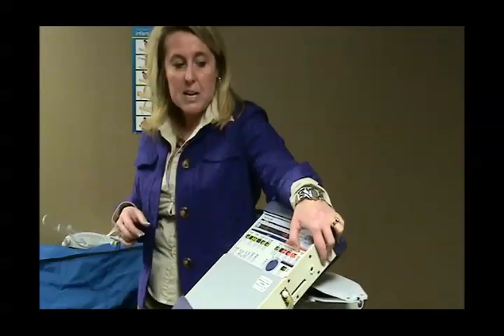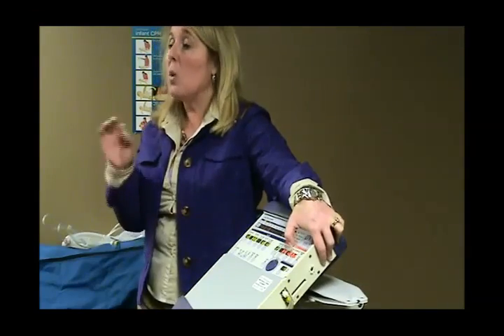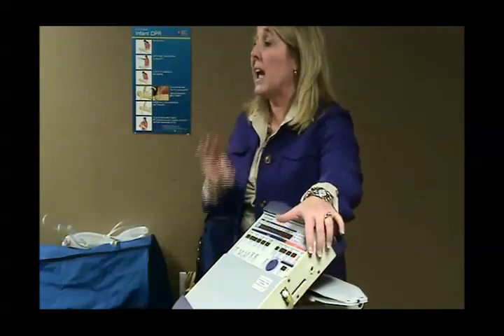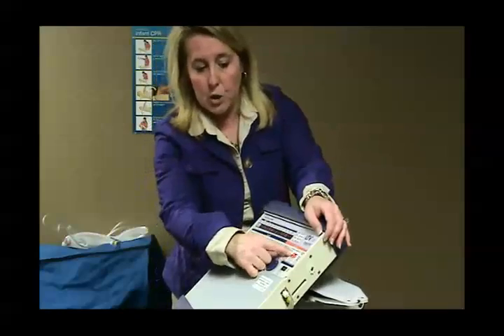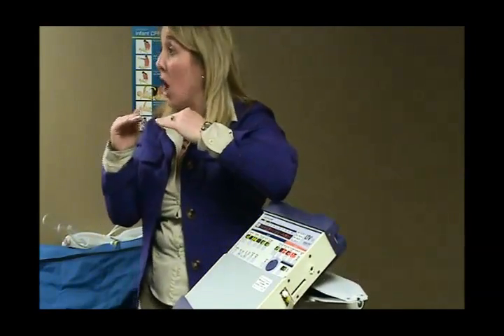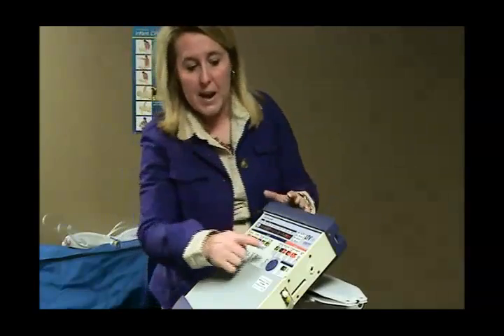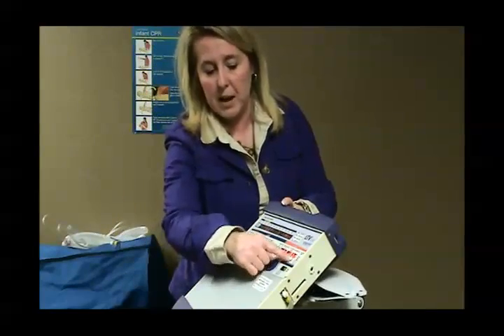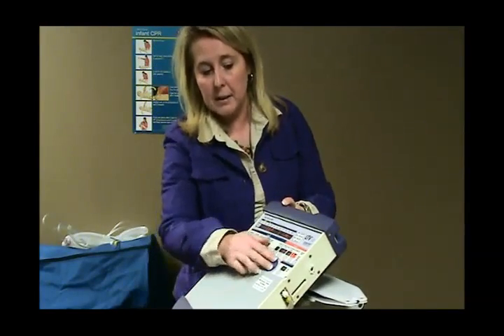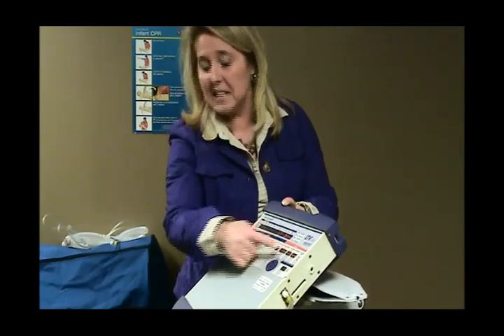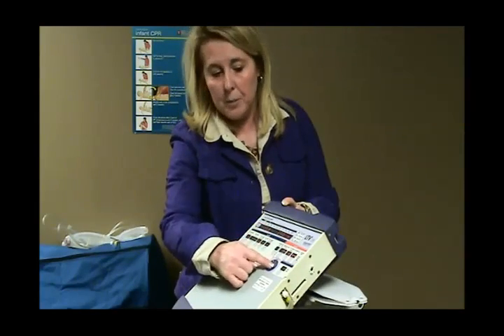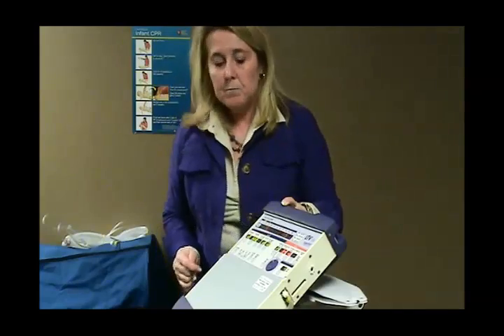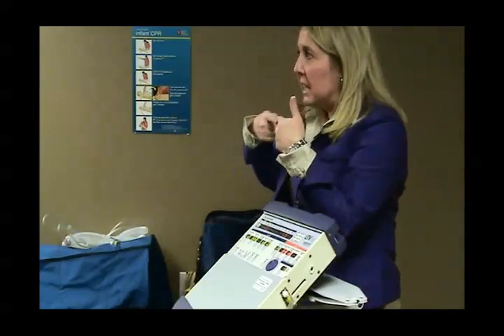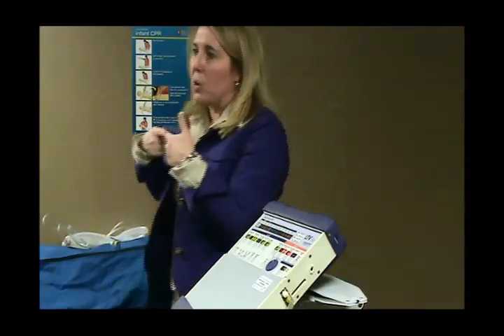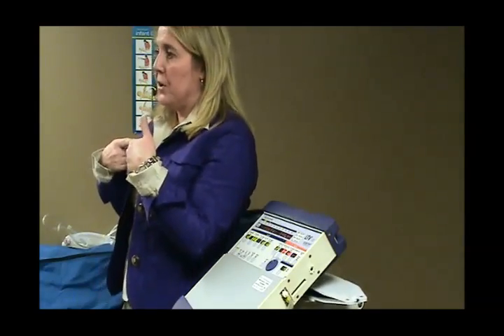If you have a patient that has a speaking valve, when we have a speaking valve, we do have to disable or turn the low minute volume alarm down to dashes, which means it's off, right? So if I have to do that, put in a speaking valve, I'm going to press that button. I'm going to turn this until I see dashes, turn my dial, and then I'm going to press it again. When you see dashes in a window, it means that parameter or alarm is turned off. Okay?